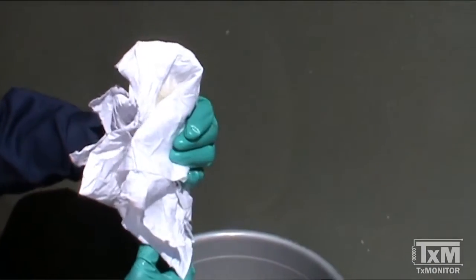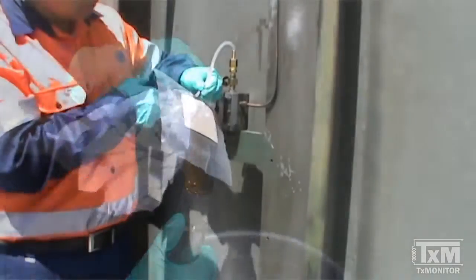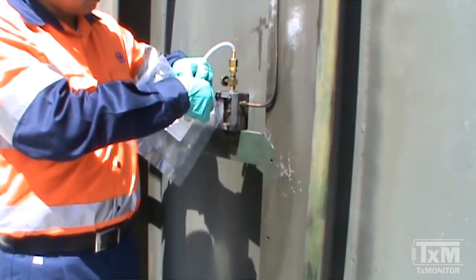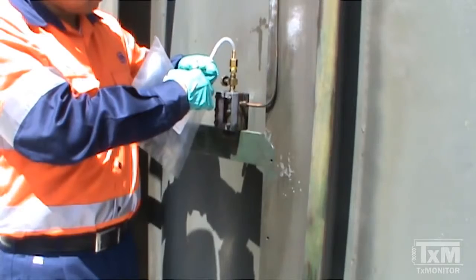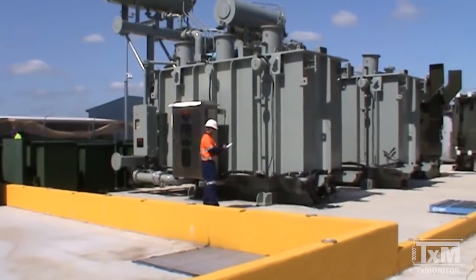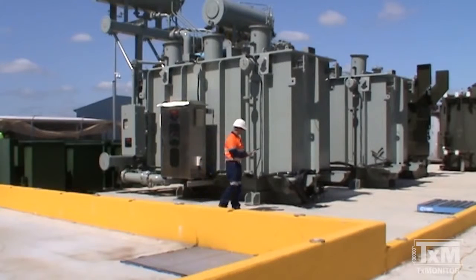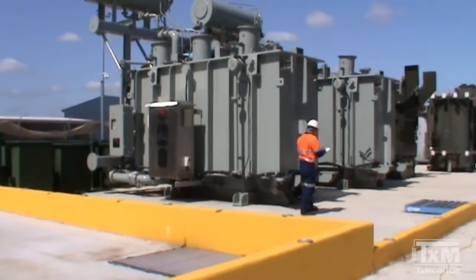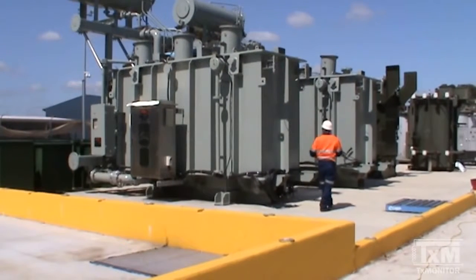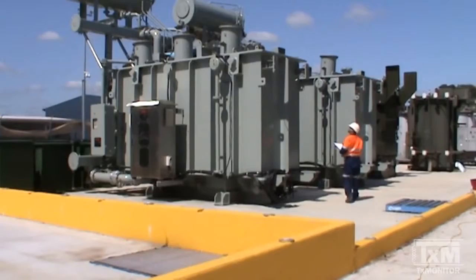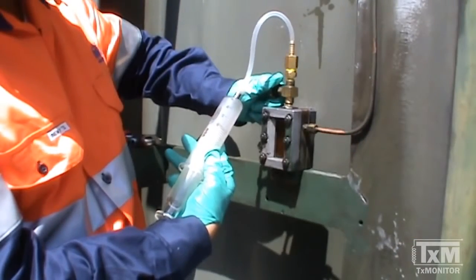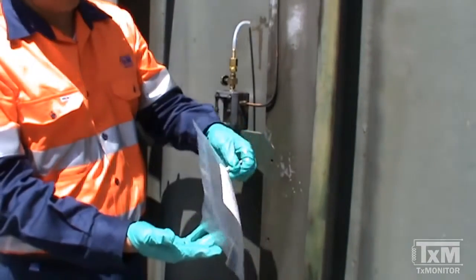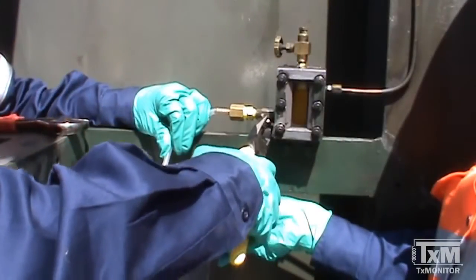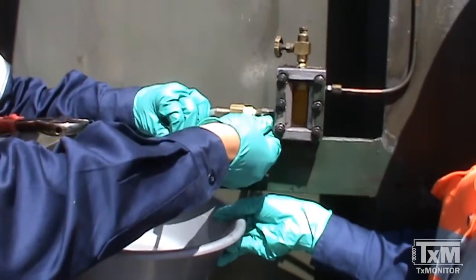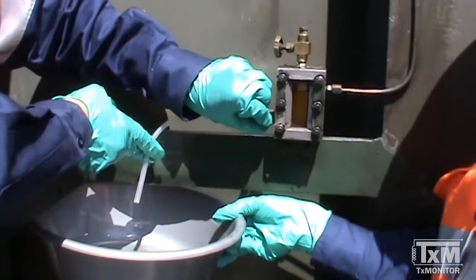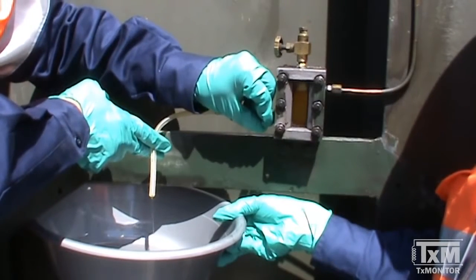A Buchholz can be either sampled for oil or gas. In this video, the techniques for sampling both are demonstrated. If the Buchholz contains accumulated gas that needs to be sampled, the gas can be retrieved using a variety of sampling containers. In this video, the sampling procedures for glass syringes and gas sampling bags are shown. Regardless of the sampling container, the first task is to bring the accumulated gas in the Buchholz to the sampling device. In order to do this, perform the following steps.